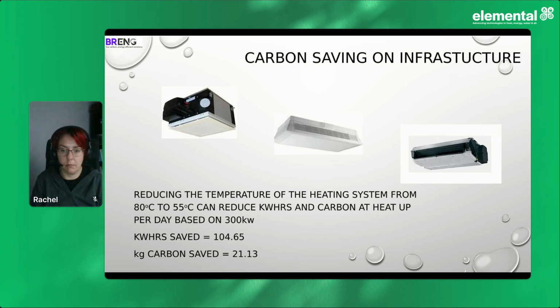So if we look at a typical 300 kilowatt school, if we didn't heat that water up to 80 degrees and only took it up to 55, kilowatt hours saved would be 104 kilowatt hours in that day. And that would be repeated every day you switch your boiler system on. We also look at the carbon saved: we save 21 kilograms of carbon every time we switch that heating system on in the morning. So by just changing your heating infrastructure to start with, doing it the right way around, you are actually saving carbon and energy before you've even looked at the air-to-water heat pumps.